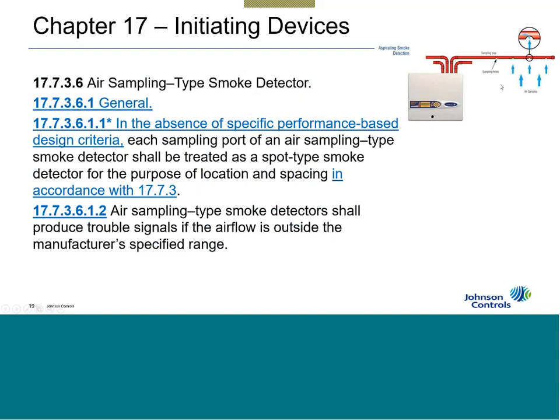Some people have taken air sampling systems and said, look, you don't need to put 20 smoke detectors in this room. I can do it with one air sampling system, and all I need is one port, and the port just pulls the air from the room, and I can detect smoke in the area. Well, that's not true. Each port needs to be tested or designed like it's a smoke detector and spaced appropriately. And there is software to make that happen.